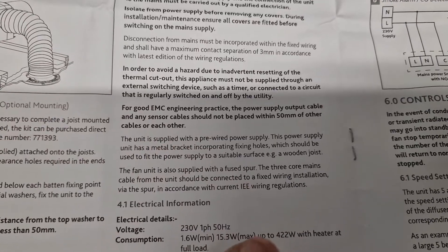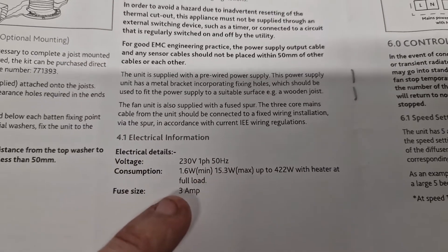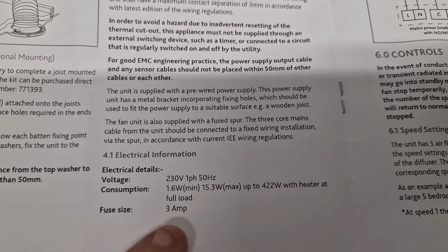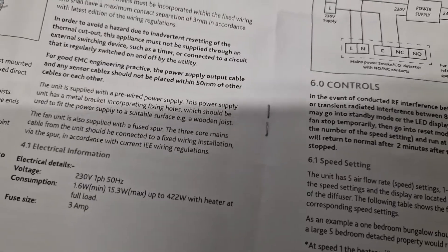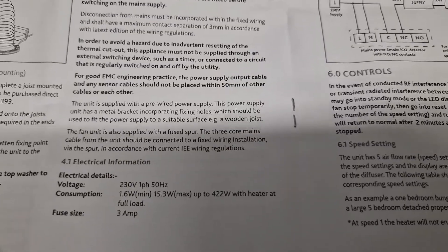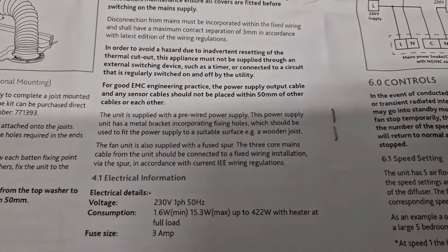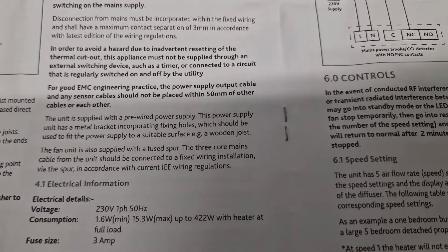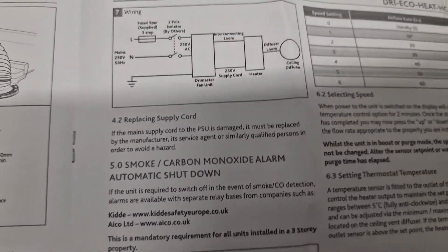You get a pre-wired power supply cable and it gives the consumption: 1.6 watts minimum, 15.3 watts max, up to 422 watts with the heater at full load on a 3 amp fuse. The heater isn't consistently running — it pulses on and off. It will increase electrical consumption but the payback is you can reduce your heating bill, and equally you're reducing any damage from condensation and mould, so it's well worth going forward once the survey determines it's required.